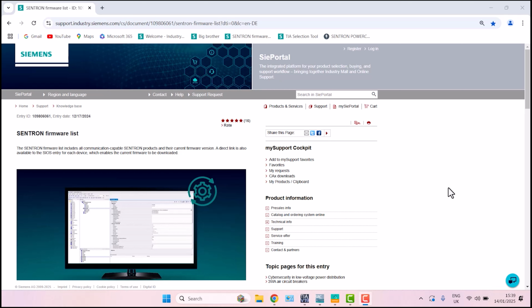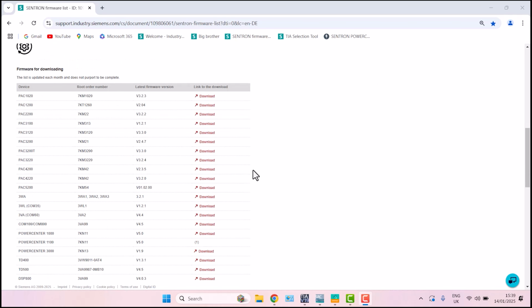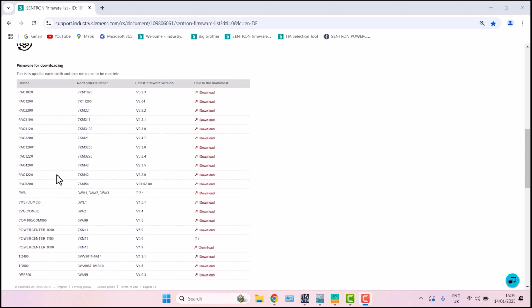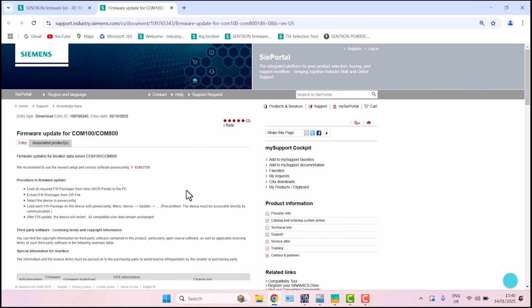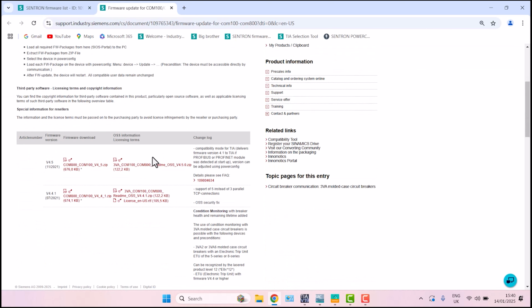If you'd like to check whether you've got the latest firmware, you need to go to the SiePortal website and look for the SENTRON firmware list. On here shows all the different SENTRON devices. Looking for the COM100 and 800, the latest firmware is 4.5. So if we're running an older firmware and we want to upgrade to the 4.5, simply click on the download link. It'll send you to a new page which gives you the option to download the new firmware.